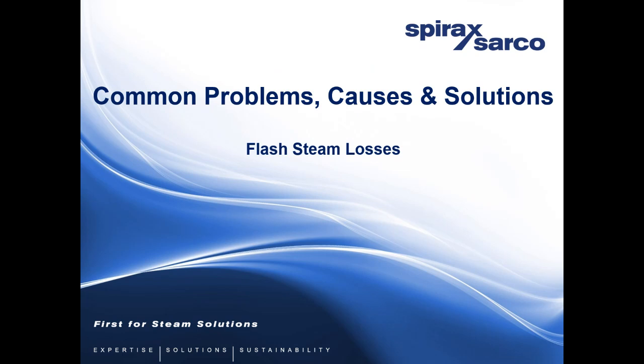If you don't have any TDS control, which many boilers in East Africa don't, it's manual rather than sensors. It means that the particulates in your boiler are allowed to build up. So we would recommend that the TDS level is kept lower than 3,500 ppm, parts per million. Doing that manually testing would give more particulates in your boiler and therefore potentially cause more scale. Hopefully that answers that question. If there's any more information you want on any of these questions, please feel free to add another question or to message us directly.